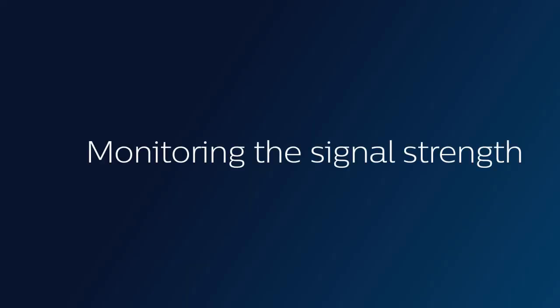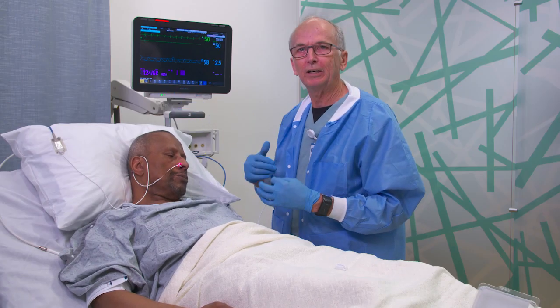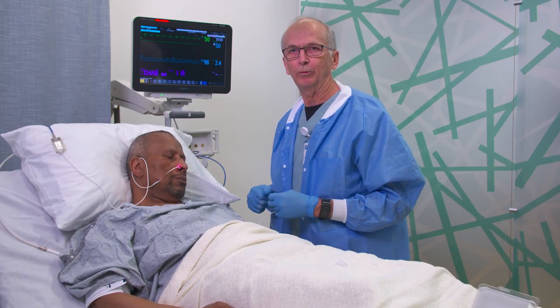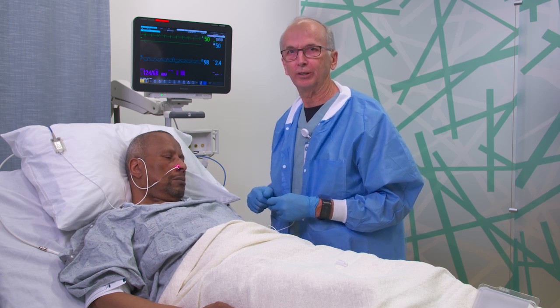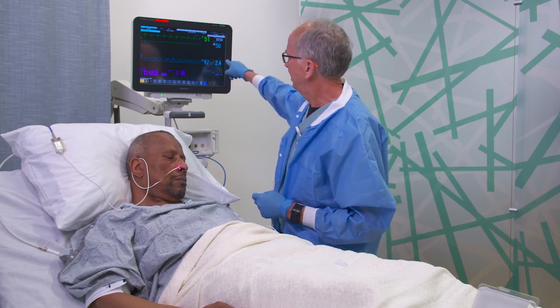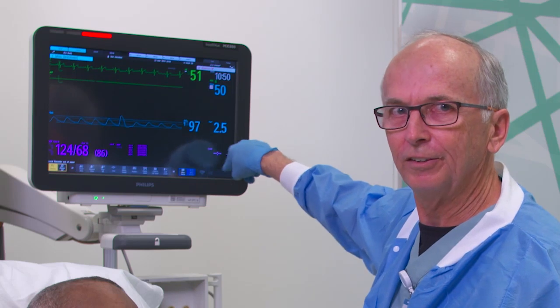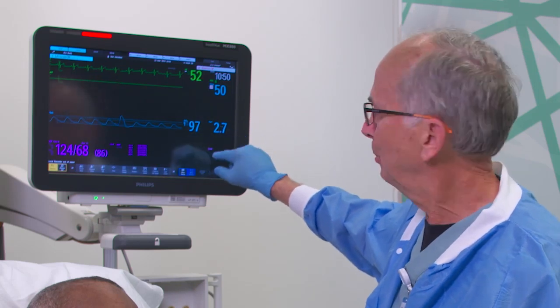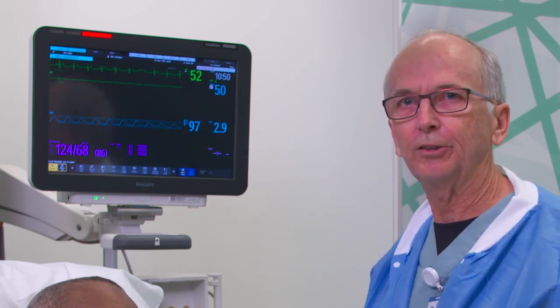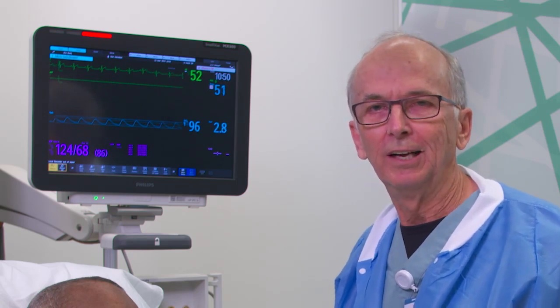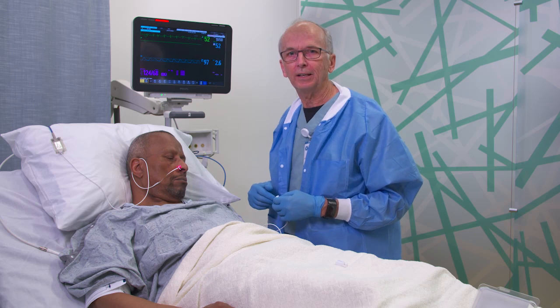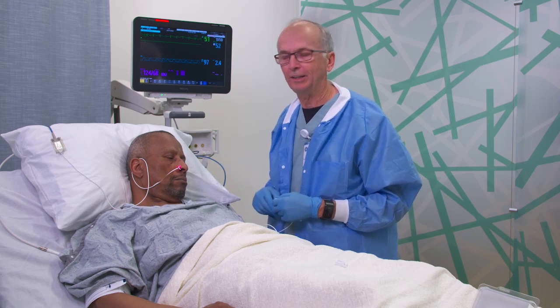The other thing you notice is you get an indication of the magnitude of the signal. The bigger the signal, the better the signal-to-noise ratio. In this case, his perfusion index, which is a unitless number, is 2.4. We consider 0.3 or higher to be an adequate number. Ideally, you are over 1, and I've seen this number as high as in the 20s.